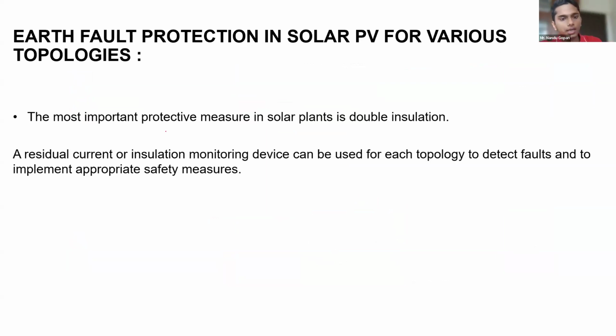So the most important thing in a solar PV, 100% you are supposed to have double insulation. Even in the combiner box, you are supposed to have double insulation. That can never be compromised. And for all protections, they will be using two devices: a residual current monitoring device, or an insulation monitoring device. By the principles of these two devices, they have implemented safety measures that detect the faults and trip the overcurrent device or whatnot. So 100% you'll see these two devices used in the topologies.